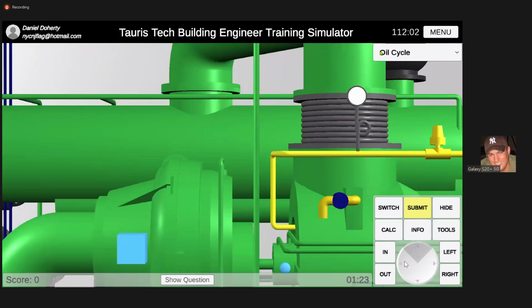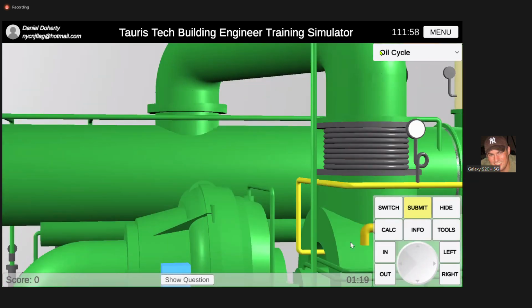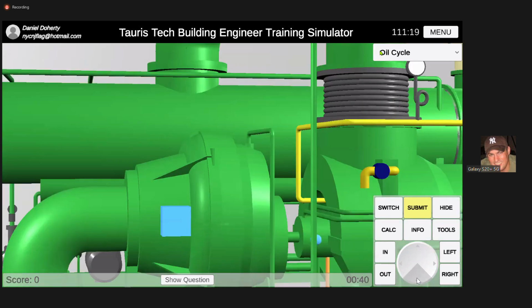Now on Metrotech, there's a gravity basin on top. It's like floating in the air. So this line here actually goes to that basin, to that sump actually. It's like a sump that's up in the air. That line goes to the sump up in the air, and then the oil comes out of that sump and feeds your compressor. The reason being is that if you lost power on the compressor, this sump that's up in the air is maintaining oil on the compressor with gravity. So the oil will still go down the compressor if you lost power. And that's the oil system.